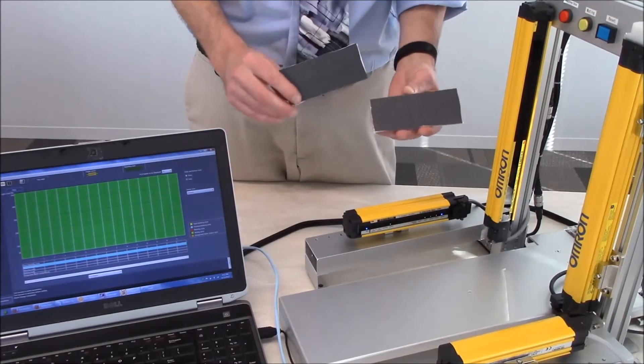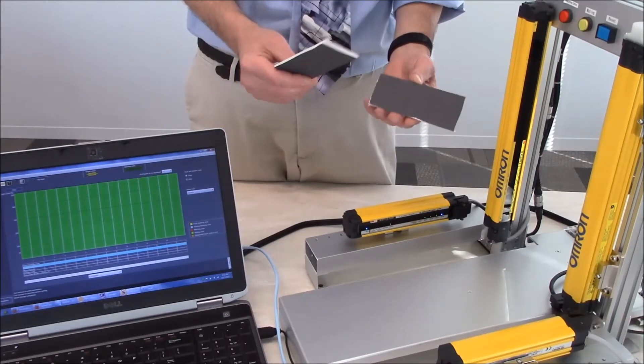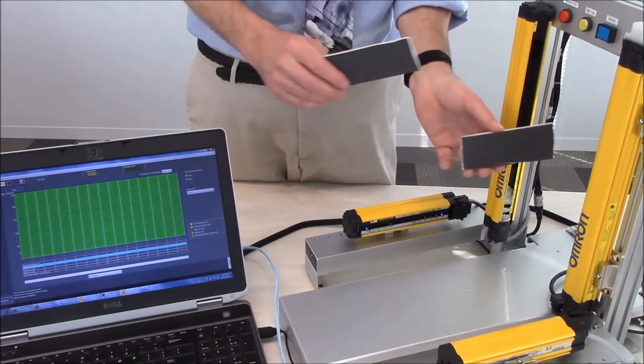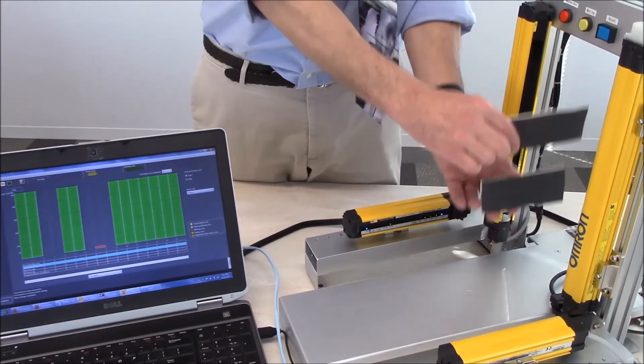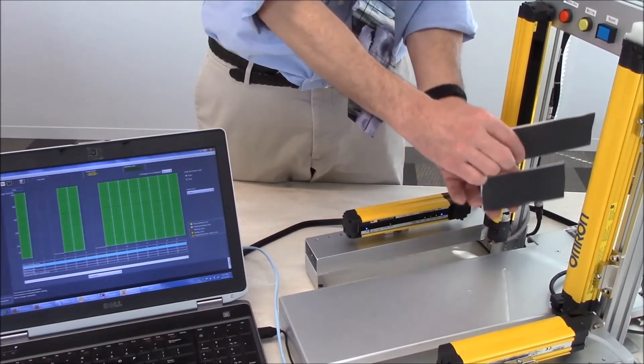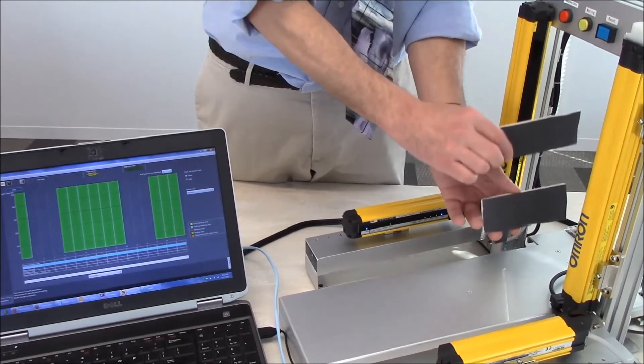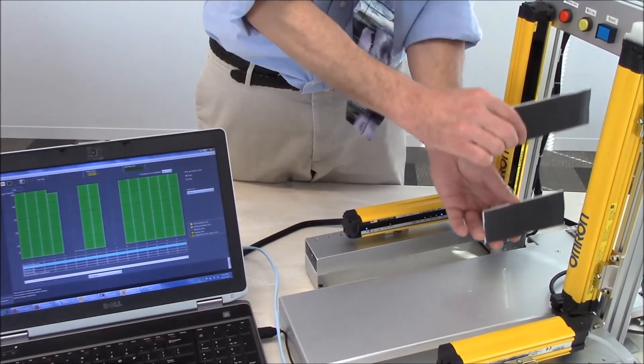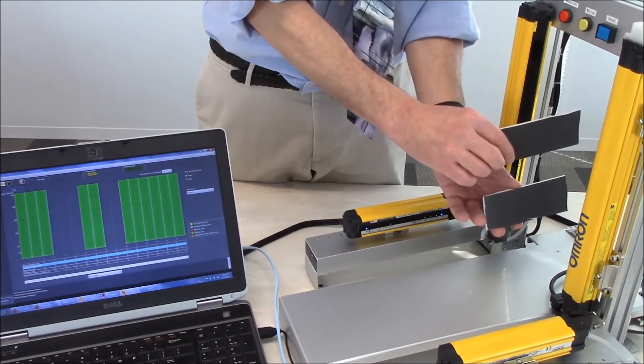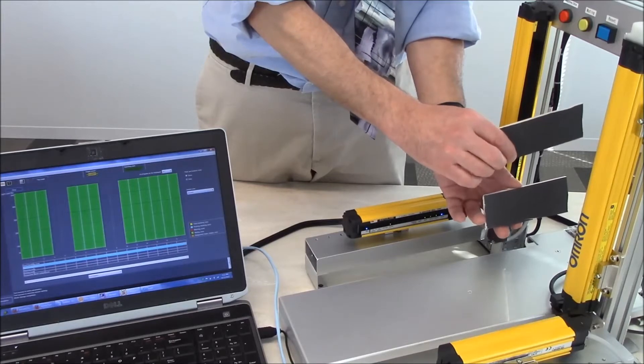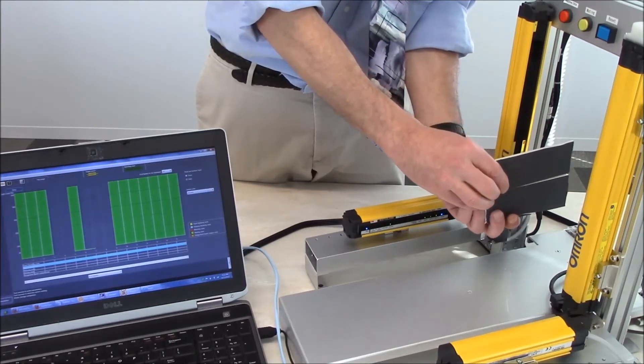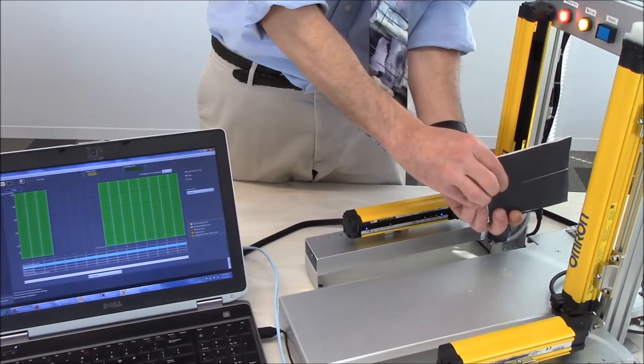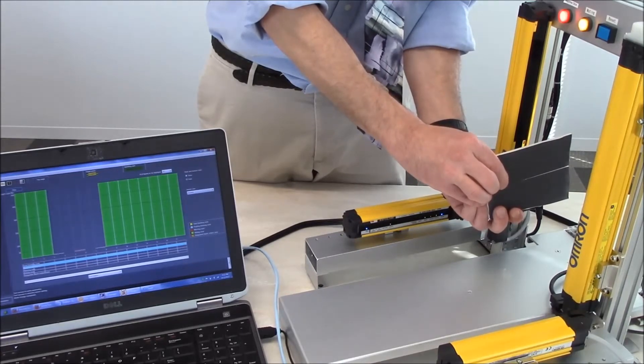Now presently I have a couple items here that are less than 3 beams in size, so I can throw them in the light curtain anywhere. I can move them up and down as you can see on the PC, I can move them apart, but as long as I don't break more than 3 beams, I am ok. The instant that I join them, I break the light curtain because I am breaking more than 3 beams.